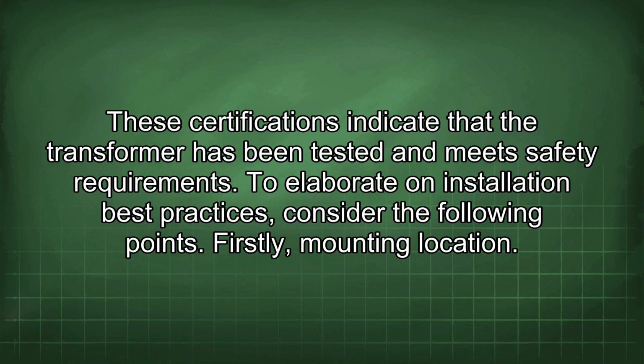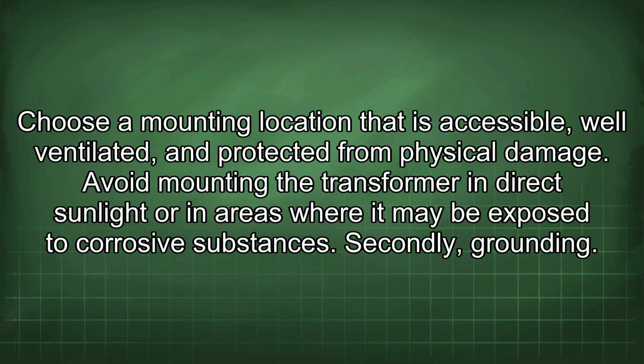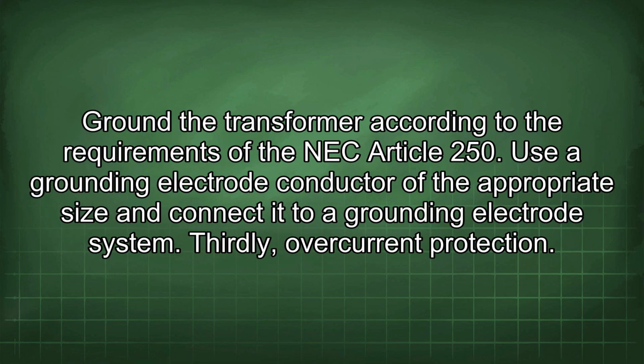To elaborate on installation best practices, consider the following points. Firstly, mounting location. Choose a mounting location that is accessible, well ventilated, and protected from physical damage. Avoid mounting the transformer in direct sunlight or in areas where it may be exposed to corrosive substances. Secondly, grounding. Ground the transformer according to the requirements of the NEC Article 250. Use a grounding electrode conductor of the appropriate size and connect it to a grounding electrode system.